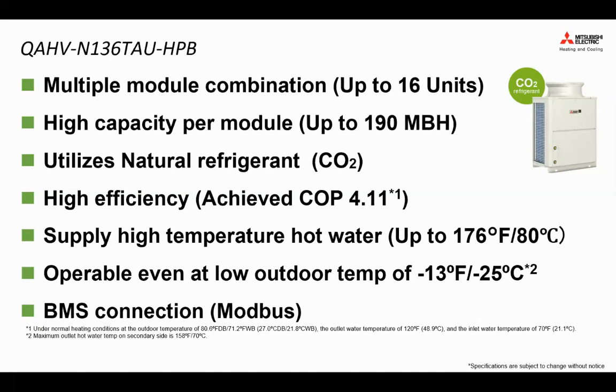It depends on its mode of operation and also the conditions. It utilizes natural refrigerant, as mentioned before. It uses CO2 with a global warming potential of 1. So compared to other types of refrigerant, it is very environmentally friendly, and it has high efficiency. The COP can be 4.11, depending on your application. And actually, the CO2 unit can also reach up to 3.83 when your inlet is 21C and your outlet is 65C on a typical hot summer day of 80 degrees Fahrenheit outside.